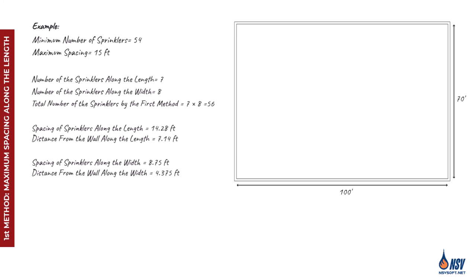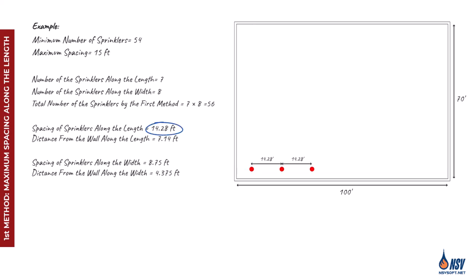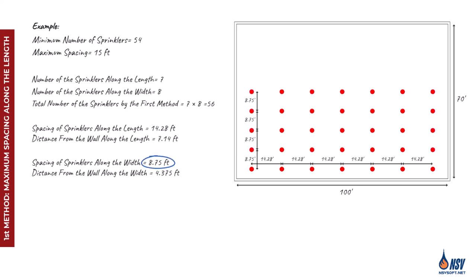Now we have all the necessary data to locate the sprinklers, including how many are required across the length and width of the room as well as their spacing. To locate the first sprinkler, we begin at one corner of the room and draw parallel lines along the length and width, each set at a distance equal to half the calculated spacing. The point where these two lines intersect marks the position of the first sprinkler. From there, we copy this sprinkler using the calculated spacing along both directions, placing all required sprinklers uniformly across the space.